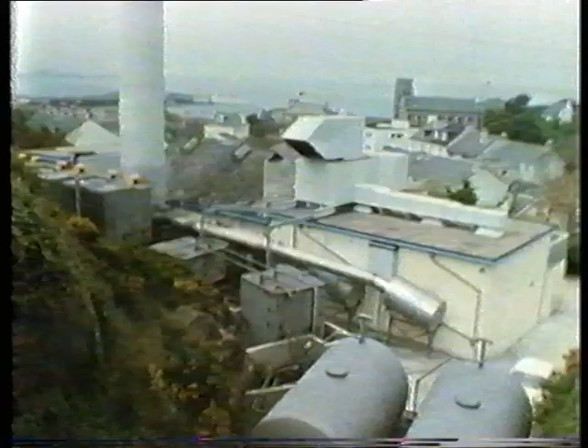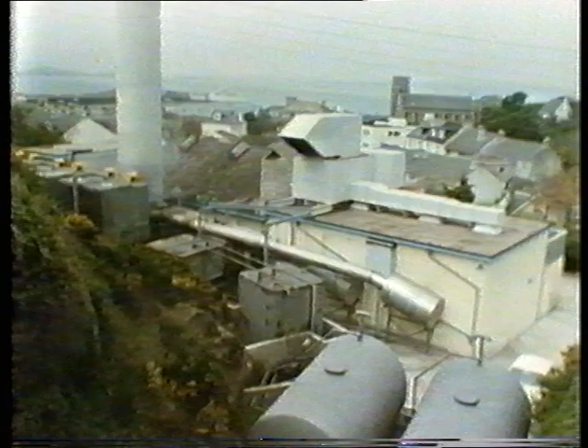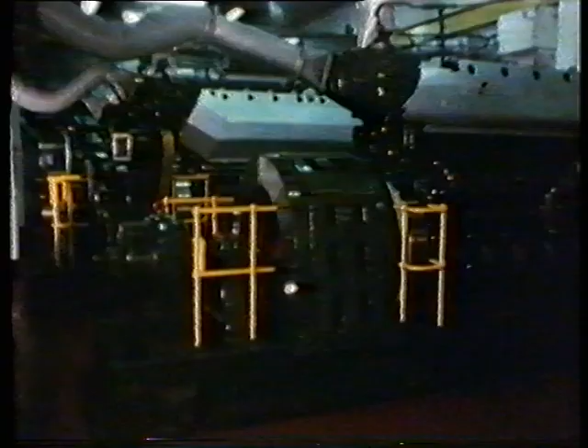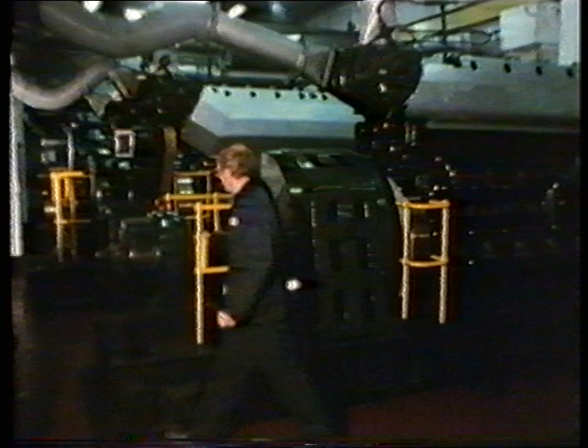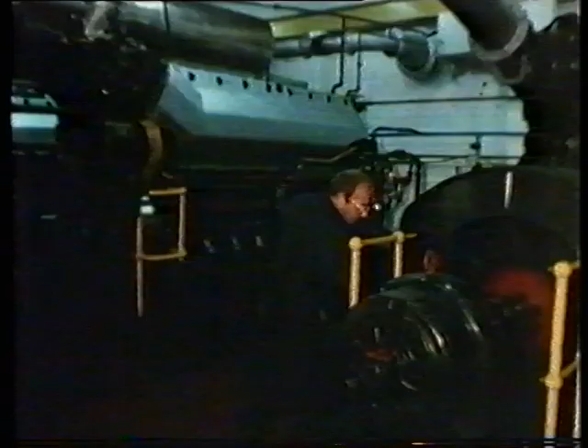Most of the population live on St. Mary's, by far the largest of the islands, and the nerve centre of the whole Scillonian lifestyle. The local council offices are here, so are banks, shops and hotels, and also the power station run by the Southwestern Electricity Board. For years, the station supplied only St. Mary's, using 6 generators with a total capacity of 3.5 megawatts of power. 2 of those generators operate at 11,000 volts, the other 4 at low voltage, which is then stepped up to 11,000 at the switchboard. At the switchboard too, the power is distributed to feeder circuits which carry the electricity to people in the town and country areas, and also to the larger undertakings such as the hospital.